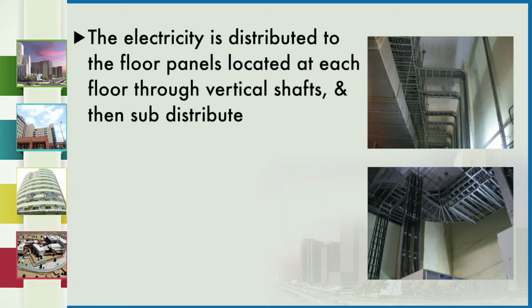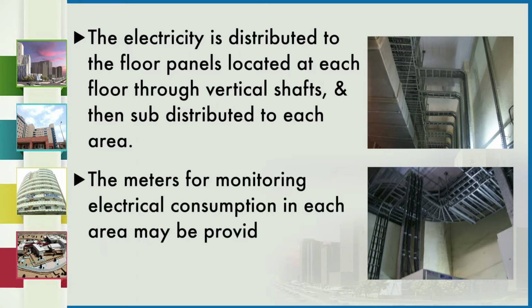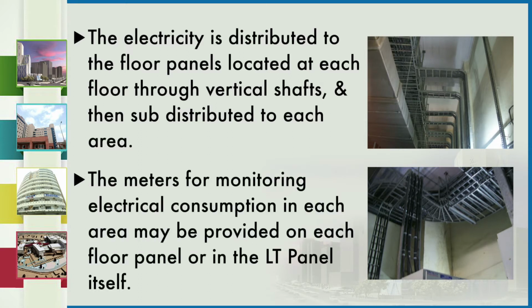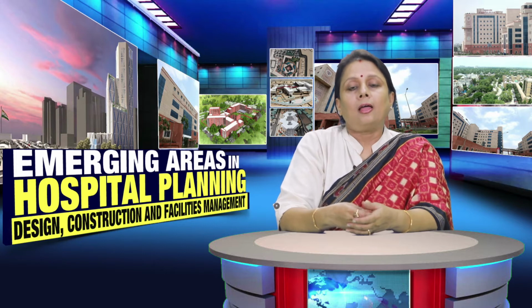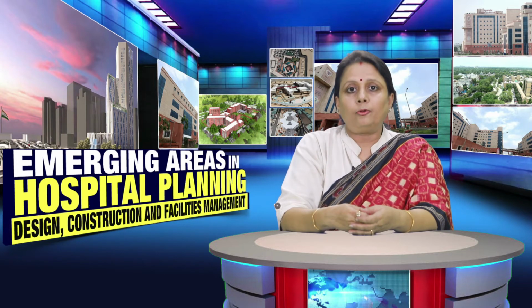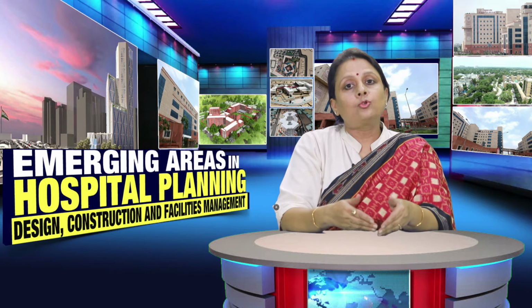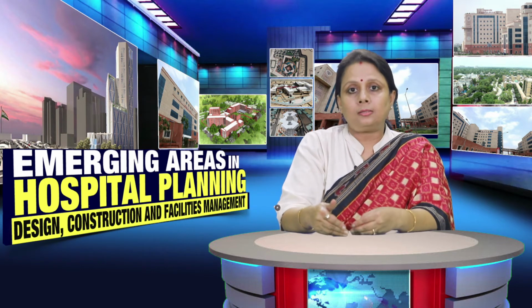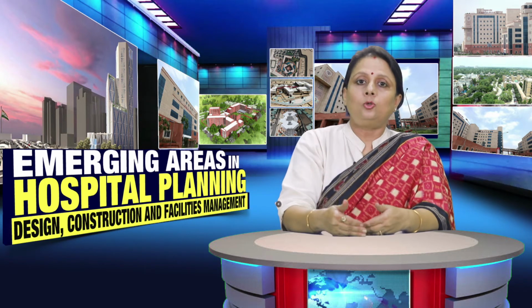The electricity is distributed to the floor panels located at each floor through vertical shafts and then sub-distributed to each area. The meters for monitoring electrical consumption in each area may be provided on each floor panel or in the LT panel itself. All critical areas have their own individual floor panel for electrical and their individual uninterrupted power supply or UPS, which is connected to a centralized UPS.